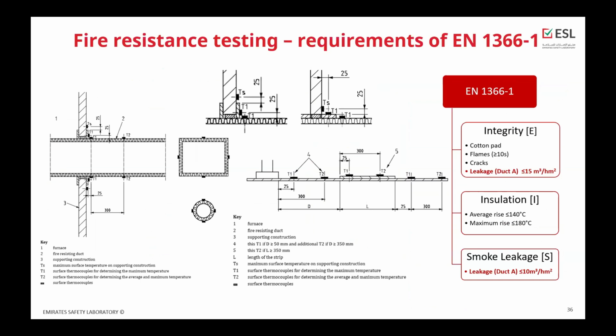The European standard also focuses more on precisely describing how the temperature criteria, the insulation, shall be assessed, providing information on where the thermocouple should be placed, at which distance from the wall, and presenting some examples of fire stopping design and how to deal with this design with the thermocouples.